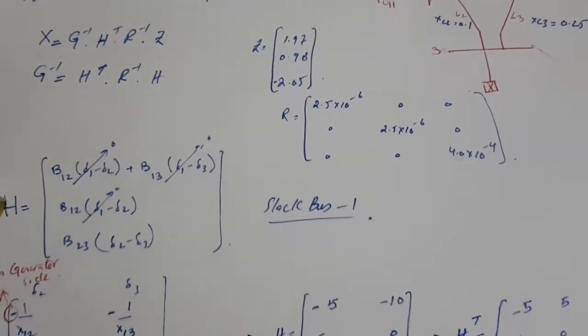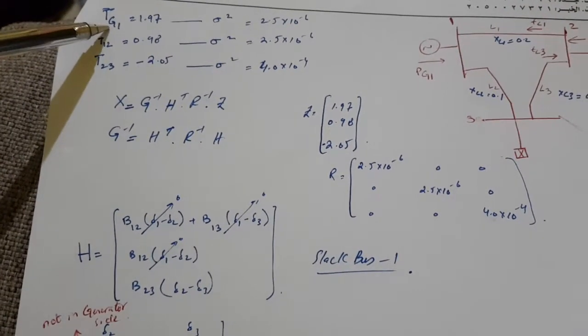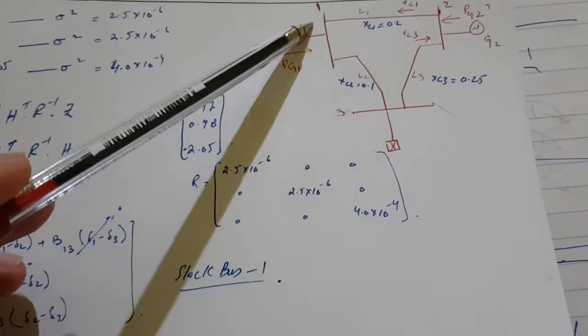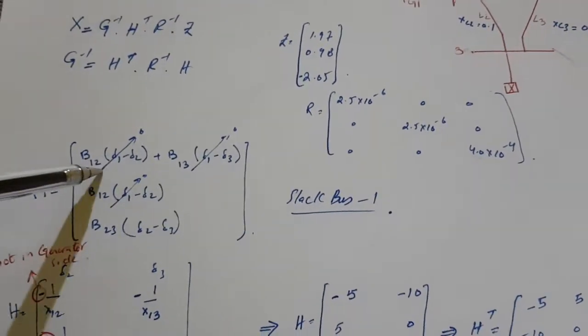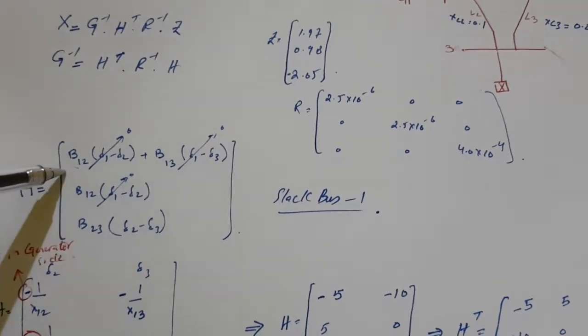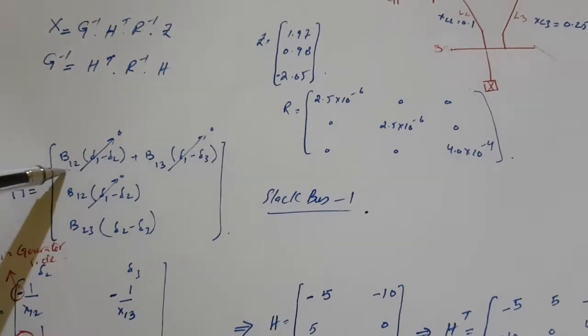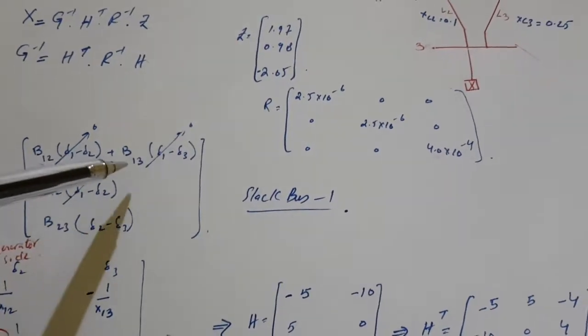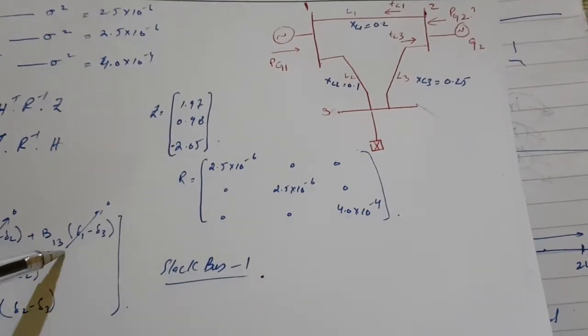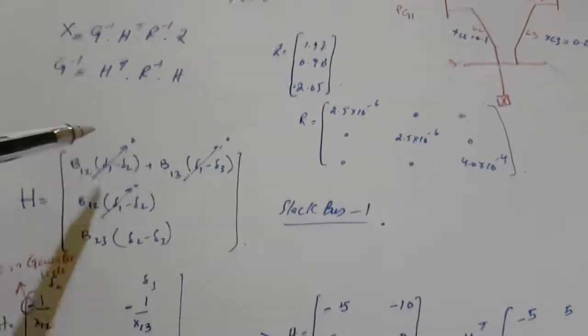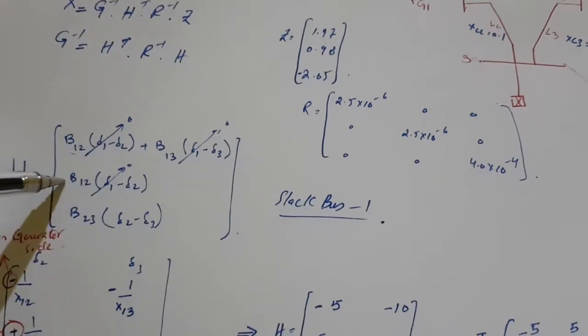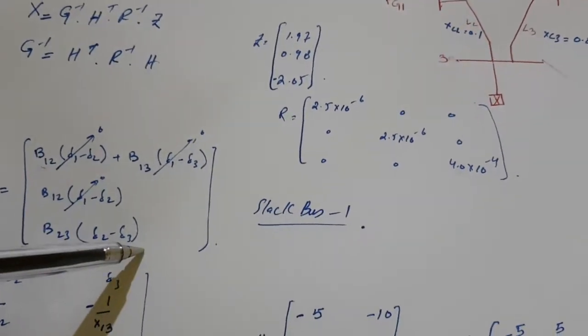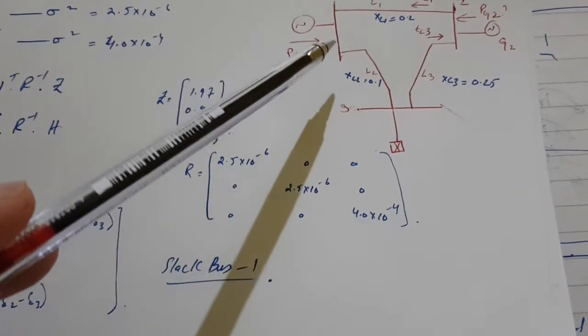The most important step in every state estimation is the H matrix. For H, the first row corresponds to PG1 — generator 1 is feeding from line 1-to-2 and 1-to-3, so you write B12*(del1 - del2) + B13*(del1 - del3). These are the state variables we have to find. Next, P12 gives B12*(del1 - del2), and P23 gives B23*(del2 - del3).